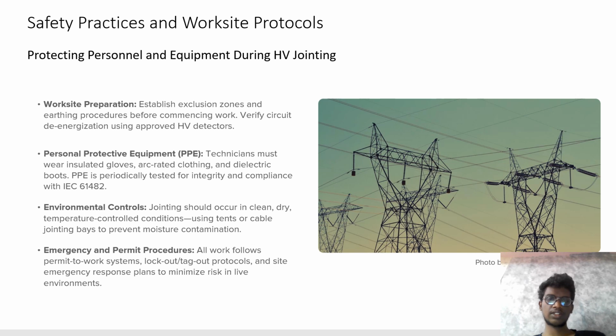Safety practice and worksite protocols: protecting personnel and equipment during HV jointing. Worksite preparation: establish exclusion zones and earthing procedures before starting work, and verify circuit isolation using approved HV detectors. Environmental control: jointing should occur in clean, dry, temperature-controlled conditions using a tent or cable jointing van to prevent moisture and contamination. Emergency and permit procedures: all work requires permit to work, lockout-tagout protocols, and site emergency response, especially in live environments.